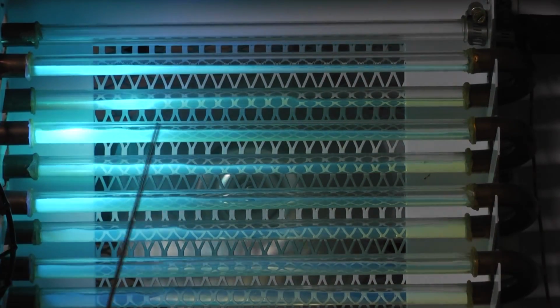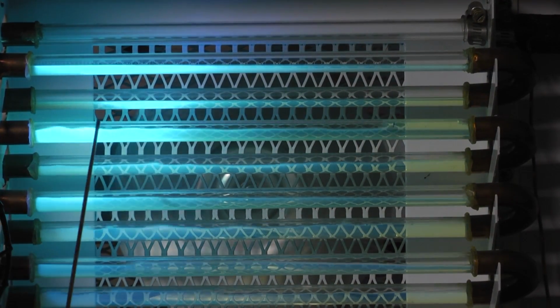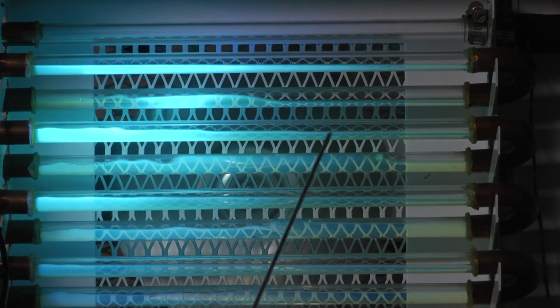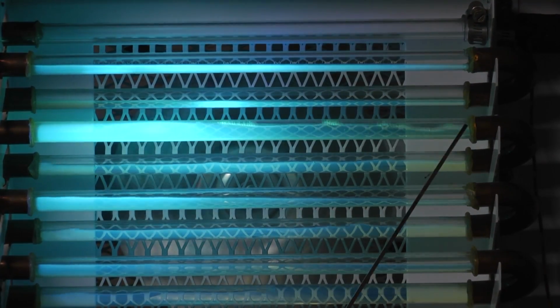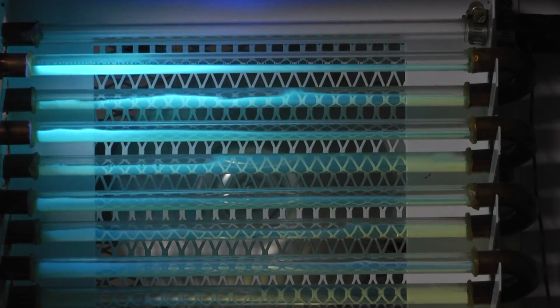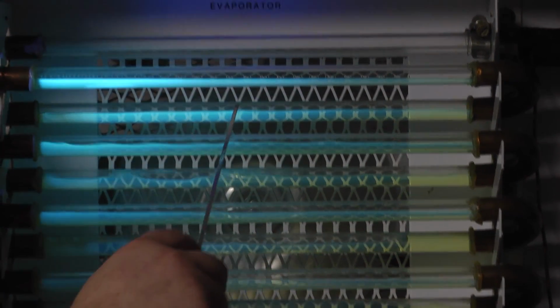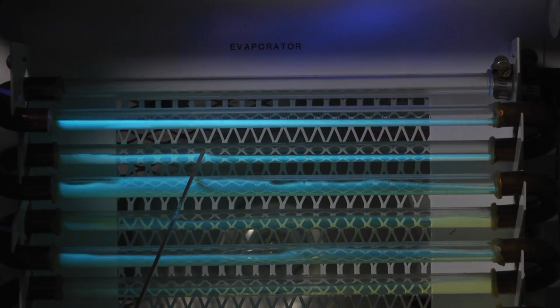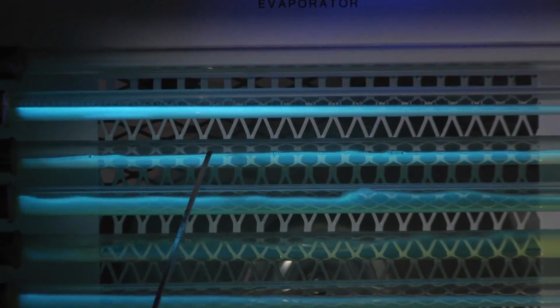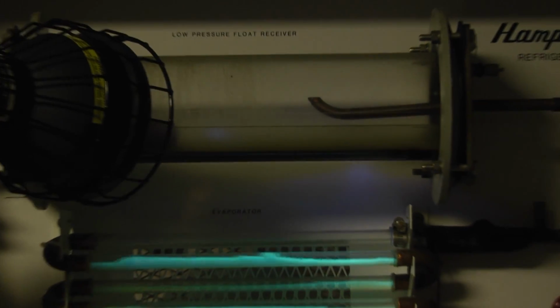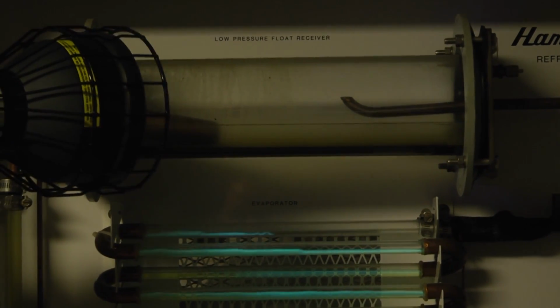As we go up to the top and we start off with more liquid here, you can actually see a dramatic decrease in the amount of liquid at the last point of the tubing. And then finally, we move back to the very back. Very small amounts of refrigerant liquid and large amounts of vapor. The next tube, we can see it happening even more. And then finally, on the last tube, you can see that we've completely evaporated the refrigerant.